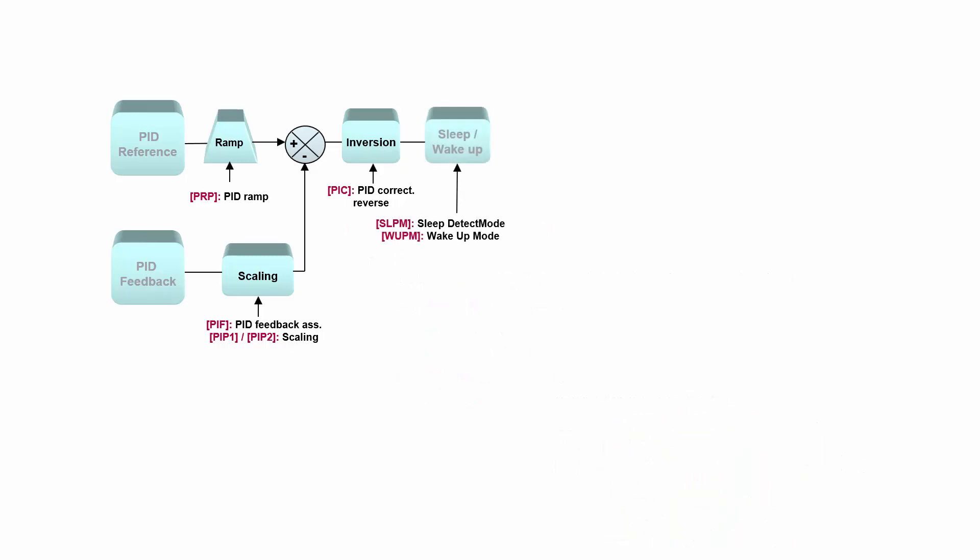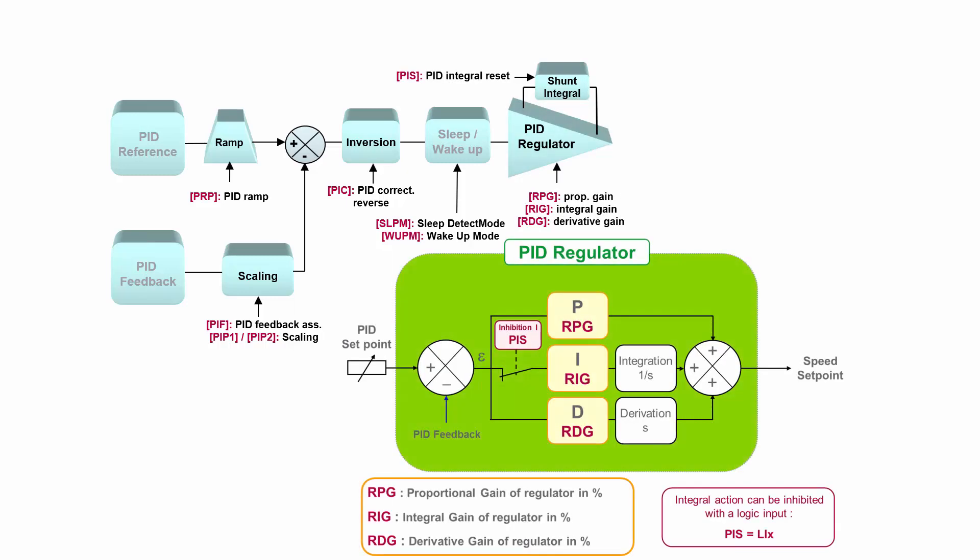After that we enter sleep/wake-up function, which we will do in a separate video, so for now we will skip it. And finally, we are entering PID regulator. A few words about PID regulator: it's a standard proportional, integration, and derivation, of which in majority of cases we are only using proportional and integral part of the PID.